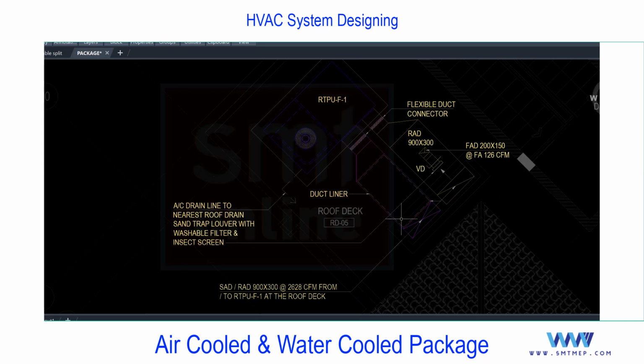If you do not use insulation, the cooling is going to be lost in the supply duct. And in the return duct, it may gain heat from outside. So the load on the coil will unnecessarily increase. The same thing is applicable even for the water cooled package also. As I said, air cooled or water cooled package, the air side system is the same.